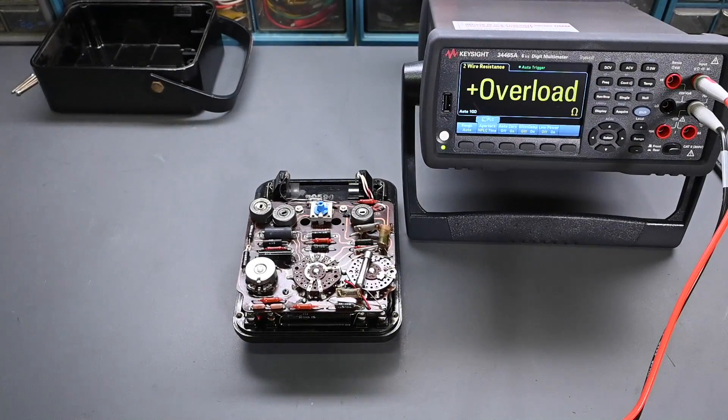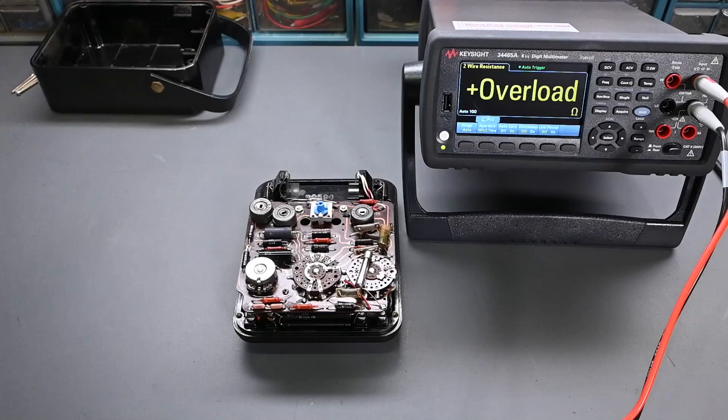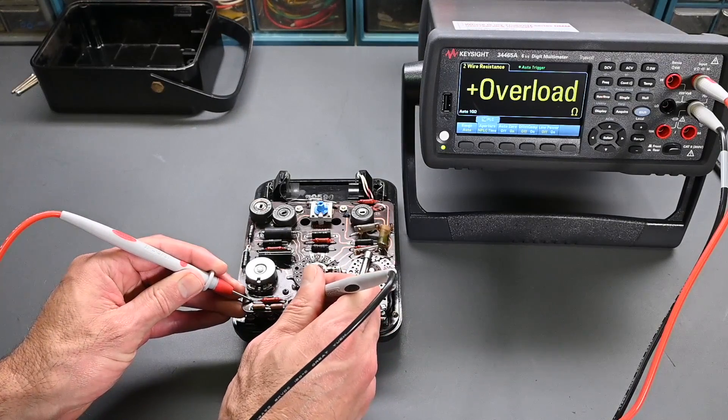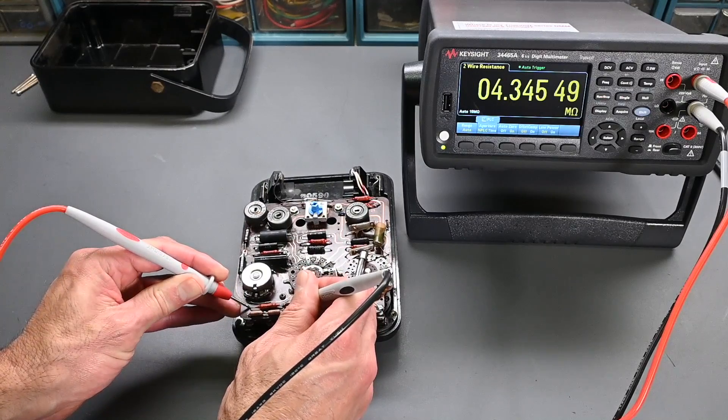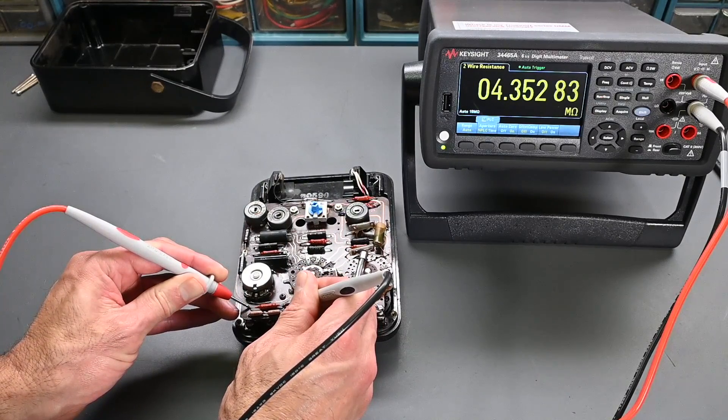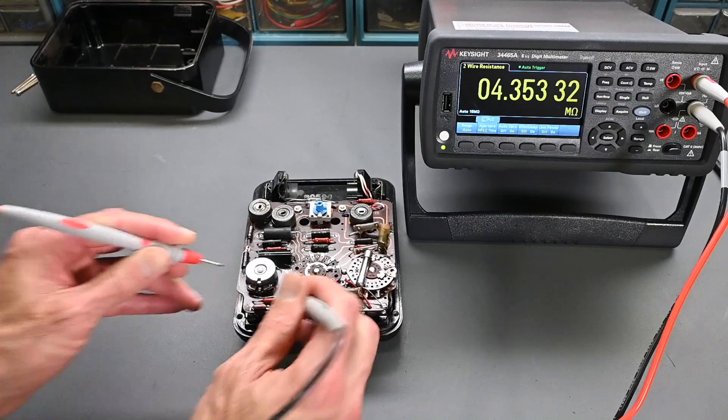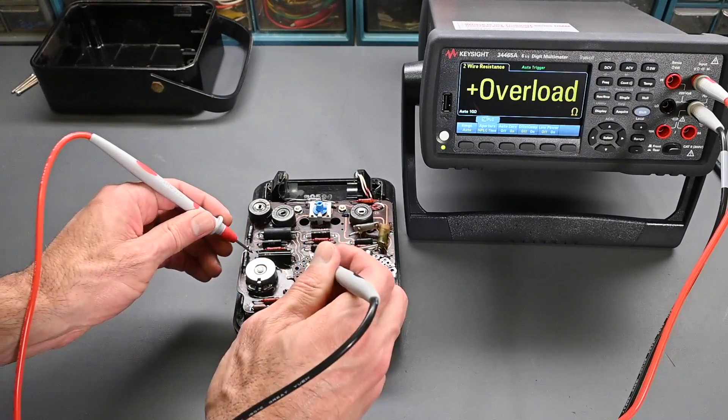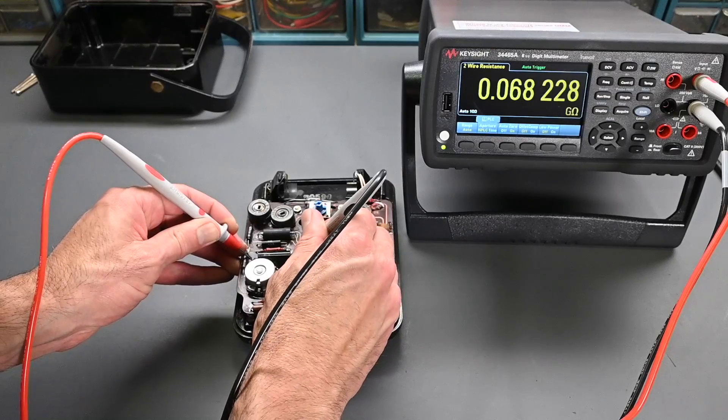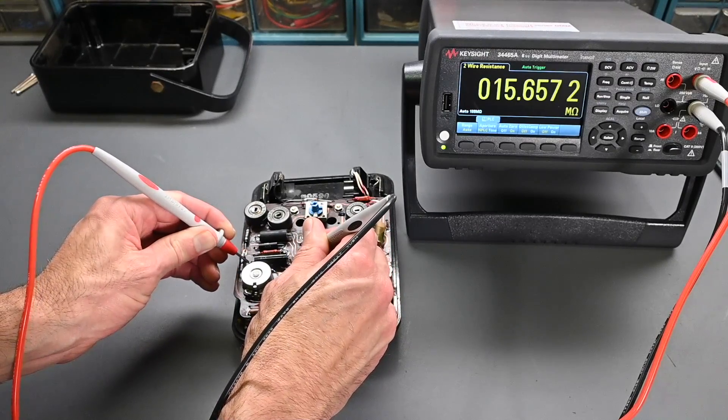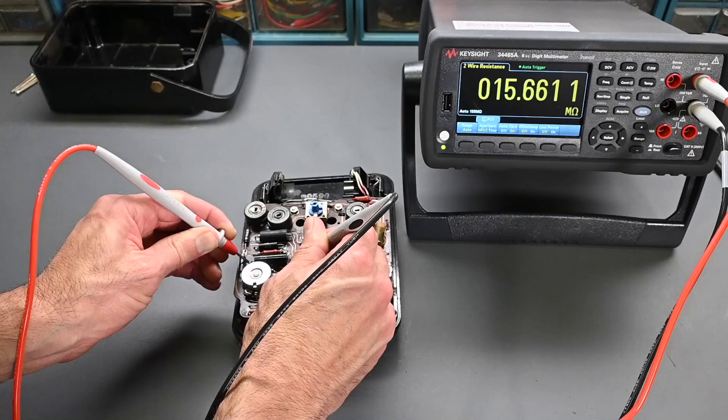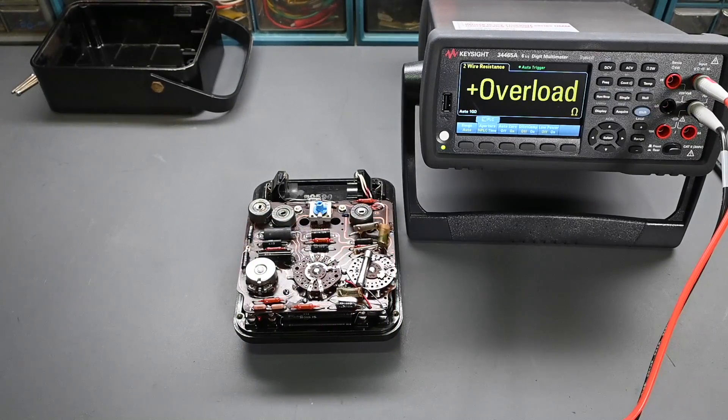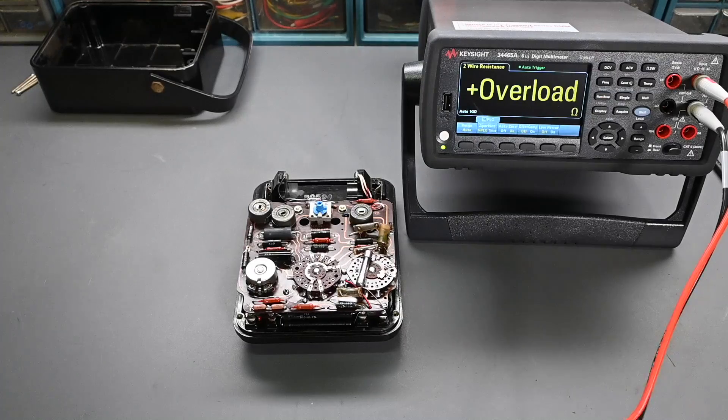So, when I left off in part 1, I didn't have those values on hand, so they needed to be ordered in. So just taking a quick look right here, this resistor should be 4 megohms, and we can see it's 4.352 megohms. So 1% of 4 million is 40,000, so that's way, way high. And this should be 15 megohms over here, and 15.6566, right around there. And 1% of 15 million is 150,000, so again, that has drifted way too high.